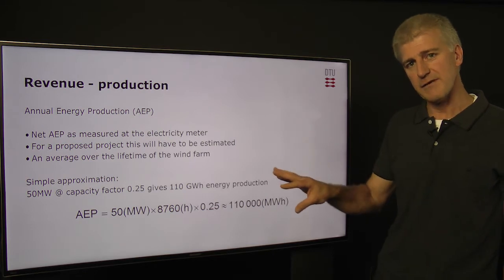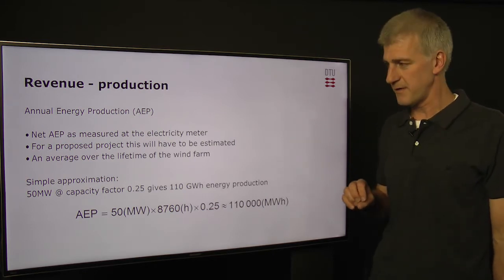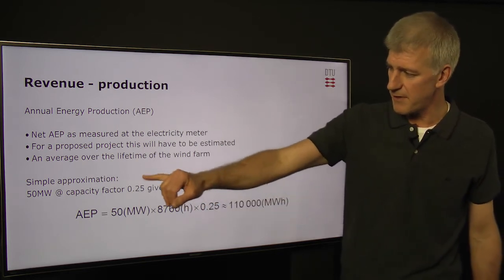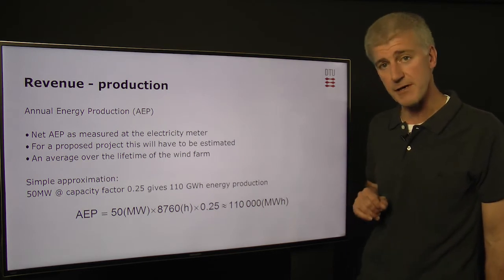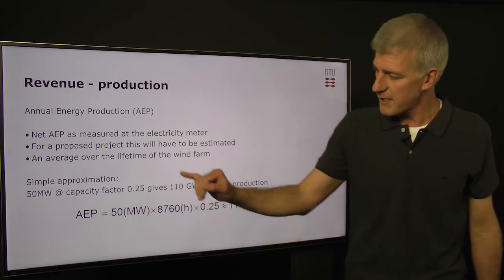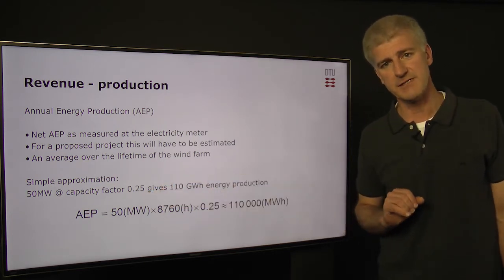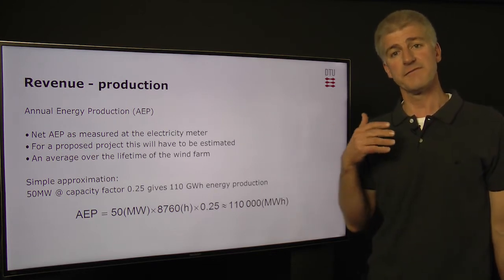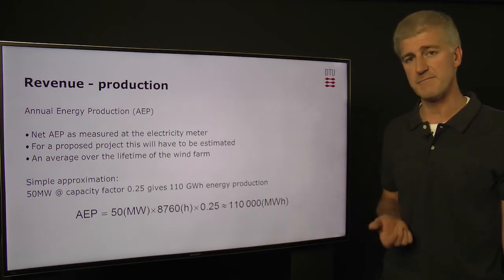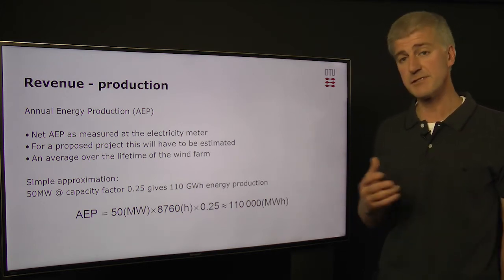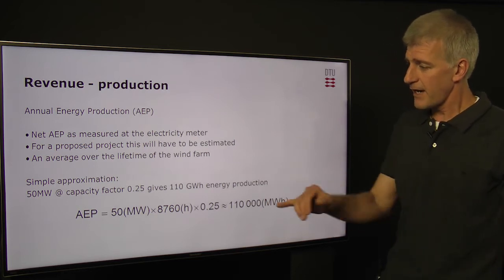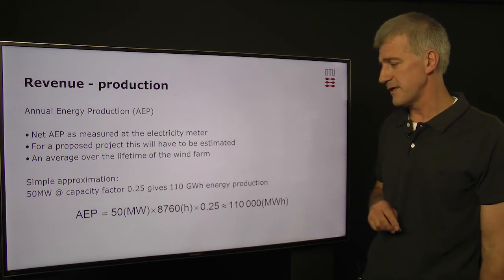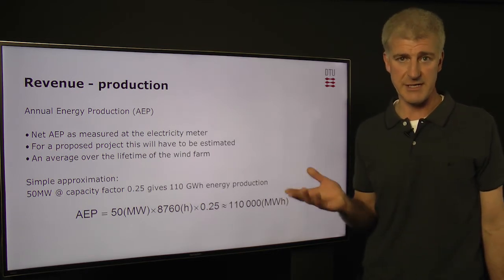Here, we're just going to look at a very simple approximation for this AEP calculation. What we need is the capacity of the wind farm — in our case, let's say 50 megawatts — and we're going to use a capacity factor of 25%. This means that, on average, the wind farm will be producing at full capacity for 25% of the time. Using these figures, this gives approximately 110 gigawatt hours of electricity generated in a year.